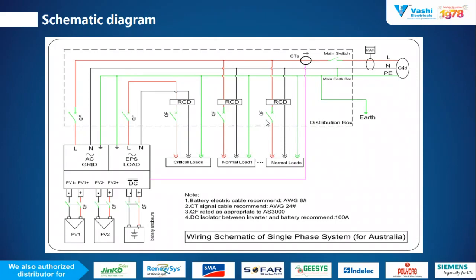Here in the image, don't consider that the critical load is only connected with the EPS system or hybrid system. It's not like that. It is connected with the grid also. Whenever the grid fails, only at that time is your inverter connected with the critical load. So this is the main noticeable part of this hybrid inverter internal circuit.